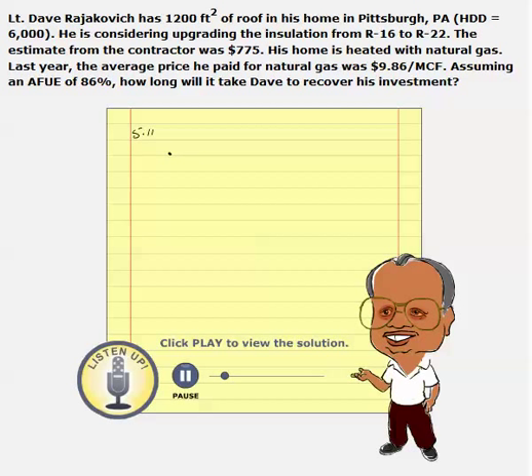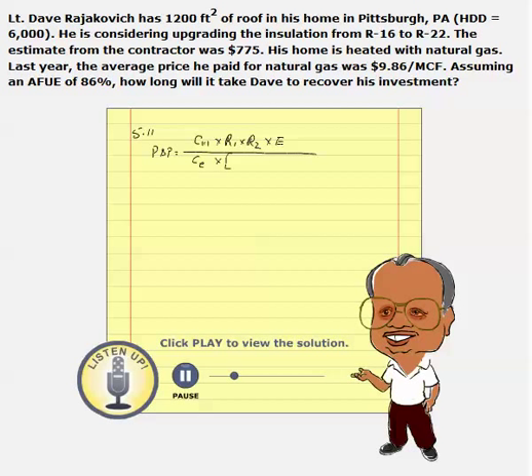This is a typical problem that uses an equation for payback period equal to Ci — cost of insulation — times R1 times R2 times efficiency, divided by cost of energy times R2 minus R1, which is the final R value minus initial R value, times HDD times 24.